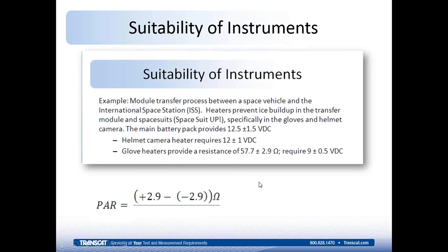So here we'll go to the 12.5 volts measurement. I'm sorry, we'll go to the 57.7 ohm measurement. And when we go back to the statement of the process that we're measuring, we said that the glove heaters have a resistance of 57.7 ohms, and the tolerance is plus or minus 2.9 ohms. So that's the process tolerance right there. In the case of the voltage measurements, you see the tolerance of 1.5 volts or 1 volt for each of those measurements there. That's the process tolerance for each of those measurements.